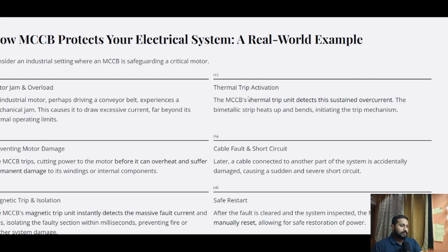Then the thermal trip activation. In this case, the MCCB's thermal trip unit detects the sustained overcurrent. The bimetallic strip heats up and bends, initiating the trip mechanism. This helps in preventing motor damage, when the MCCB trips, cutting power to the motor before it can overheat and suffer permanent damage to its windings or internal components. Then cable fault or short circuit.